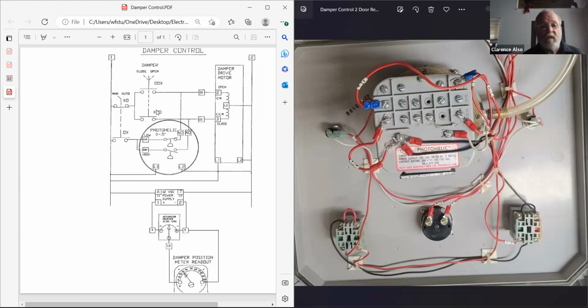This is a pressure switch. That damper thing is a vacuum switch basically, it's a very sensitive one. There's 26 inches to a PSI, and you guys are looking at like a tenth of a PSI, a tenth of an inch of water column when there's 260 in a PSI. So it gives you an idea what kind of sensitivity, at 0.1, 0.2, 0.3 - it's sensing the suction at that point. This is what's allowing all that air to come in, so this is really a very important instrument, and you should get it going.